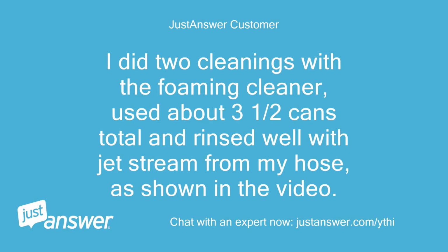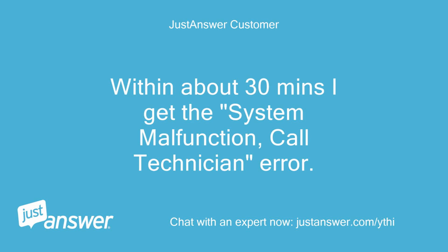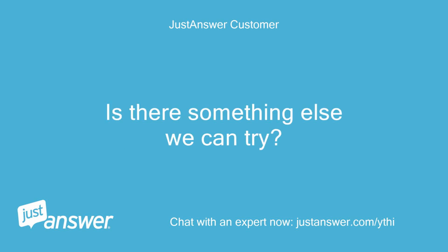I did 2 cleanings with the foaming cleaner, used about 3.5 cans total and rinsed well with a jet stream from my hose, as shown in the video. I let the unit dry for an hour and then flipped the circuit breakers back on to restart it. Within about 30 minutes I get the system malfunction. Call technician. Error. Fault code says high thermal cutout, 32 events, and high comp cutout, 10 events. Is there something else we can try?